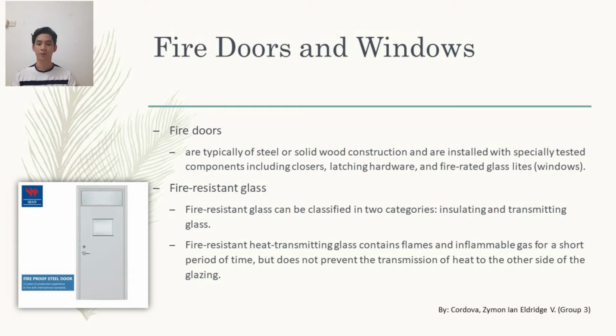Another one for fire protection is fire doors and windows. Fire doors are typically steel or solid wood construction and are installed with specially tested components including closers, latching hardware, and fire-rated glass. Fire-resistant glass. Fire-resistant glass can be classified in two categories, insulating and transmitting glass. Heat-transmitting glass contains flames and inflammable gas for a short period of time, but does not prevent transmission of heat to the other side of the glazing.